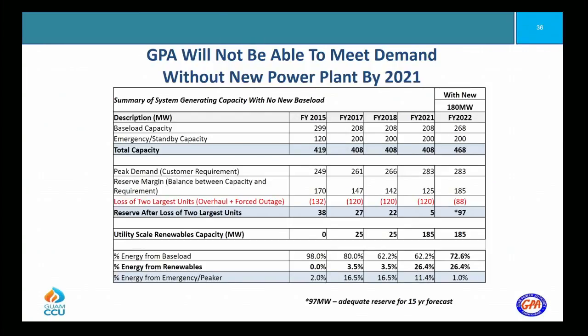With the new power plant, we've added base load. We really have enough capacity because we're going to be putting in smaller units, not the big 60-some megawatt units. If we have 66 megawatts, we have to have 132 megawatts of reserve. By putting in smaller units, the biggest unit here is the MEC 809, which is 44 times 2, or 88. So there's more power to serve everybody, because when one is under overhaul and the other fails, you still have energy to serve the public. That's how the utility does its reserve.